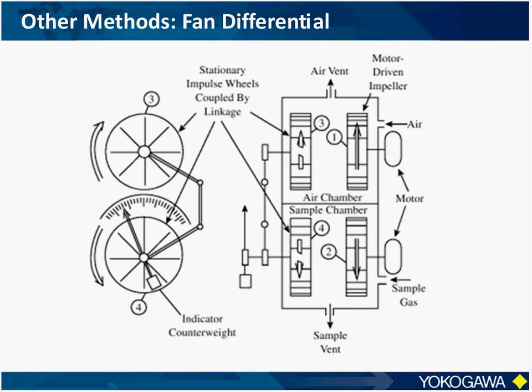Now, the impulse wheels are linked to each other, and the torques created on the wheels by the flow of the gases are directed in opposite directions. The magnitude of the torque is going to be dependent on the specific gravity of the gas. Now, this is a purely mechanical means to determine if that sample gas is lighter or heavier than the reference air.